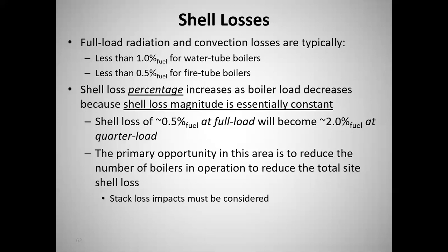I was in the Bridgestone plant in Warren County. And Bridgestone Warren, they make tires. So they're cooking tires. They're curing rubber with steam. Well, it turns out, and I didn't know this until I went down there, they're running several boilers very lightly loaded. They're running 2 or 3 boilers at 25% load. And you go, hey man, why are you running 3 boilers at 25% load? Why don't we just run 2? We could probably just run 1 and shut off 2. They say, you don't understand.